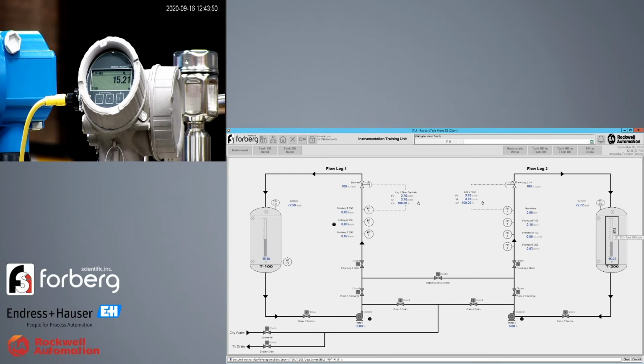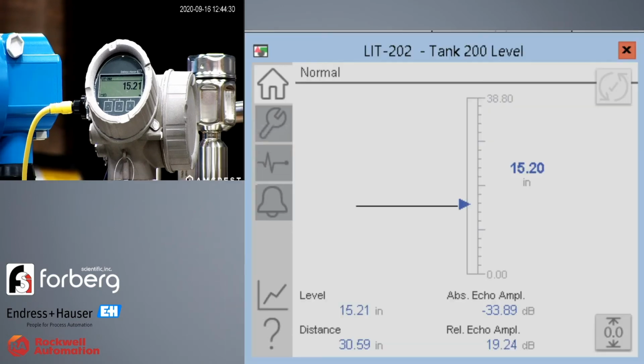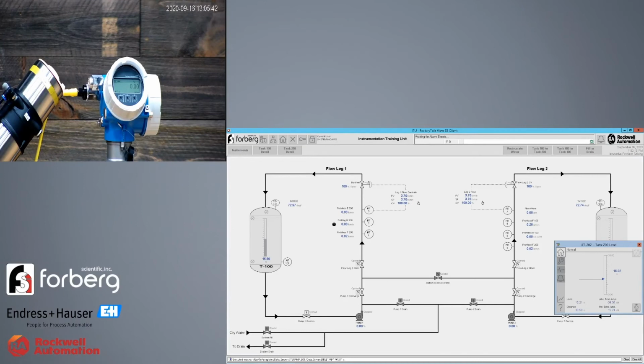So I'm going to open up the process faceplate. The primary variable you'll notice is configured for level and confirms the actual reading coming in through the 4 to 20 milliamp current loop. In this device, the other three variables are provided to aid maintenance in determining the health and calibration of the device. Next, I will turn on some of our pumps and open up the FIT4 process faceplate that drills into the Endress+Hauser ProMass F200 Coriolis mass flow meter.